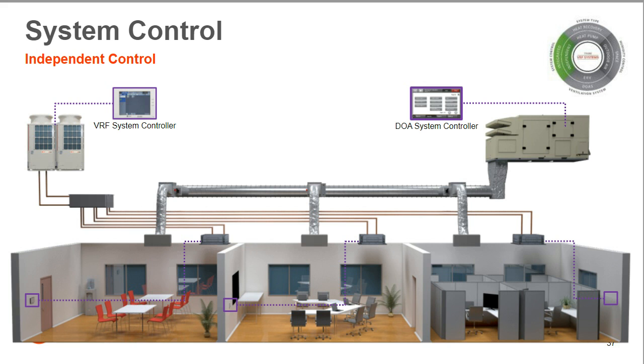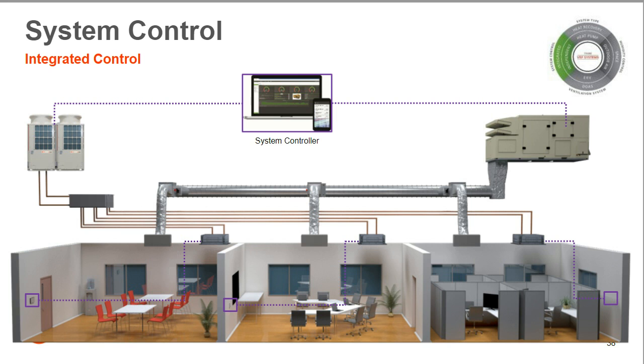These include 2 control panels for the 2 different systems, possibly from 2 different vendors, little to no coordination between the systems, and a lack of advanced building control options. Scheduling strategies like supply air temperature reset, morning warm-up, and others might not be as easily available with independent control. When it comes to integrating controls, providing connectivity can be useful. Improved connectivity can enable useful additions like dashboards, alarms, remote connectivity, and the ability to control multiple buildings.